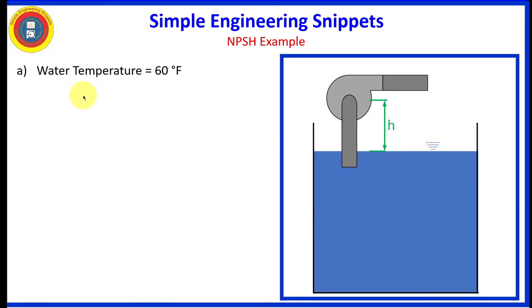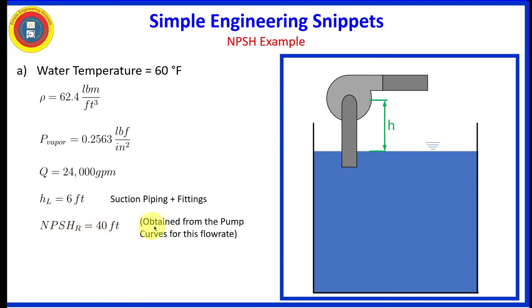Okay, so let's start up. First, water temperature is 60 degrees Fahrenheit. Provided the density, the vapor pressure, the flow rate, and the head loss in the suction piping is 6 feet. And the net positive suction head required is 40 feet, and again, that would normally be obtained from the pump curves for the given flow rate, but it is provided in this example.